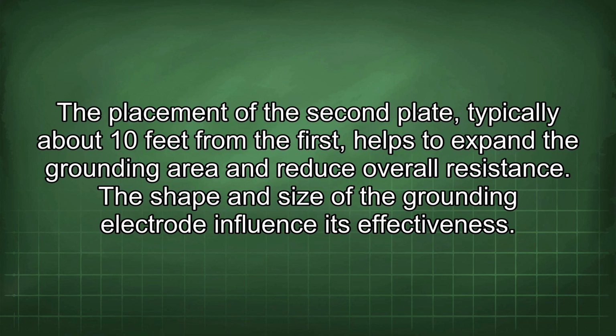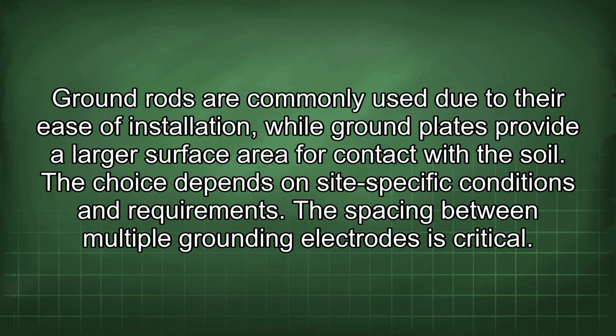The placement of the second plate, typically about 10 feet from the first, helps to expand the grounding area and reduce overall resistance. The shape and size of the grounding electrode influence its effectiveness. Ground rods are commonly used due to their ease of installation, while ground plates provide a larger surface area for contact with the soil. The choice depends on site-specific conditions and requirements.